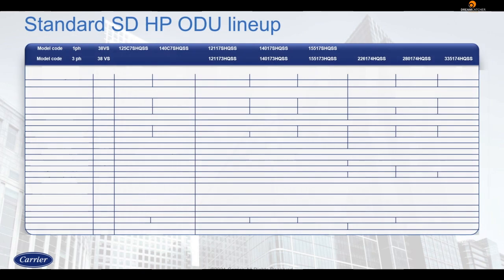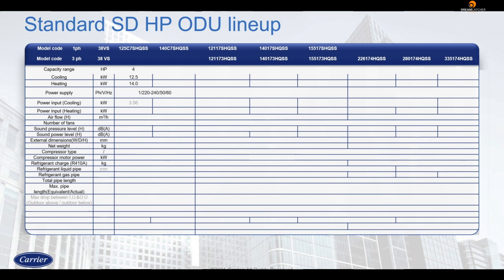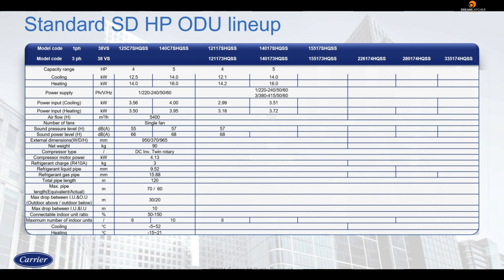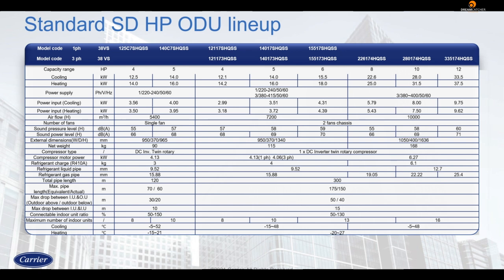The side discharge heat pump units offer a large operating range for both the one fan and two fan modules. Keep in mind that the capacities mentioned here in the nomenclature are in terms of kilowatts and not horsepower. All these models are using DC inverter twin rotary compressor technology. Also remember that the choice of single fan or double fan needs to be made keeping in mind the piping length and the number of indoor units that need to be connected.